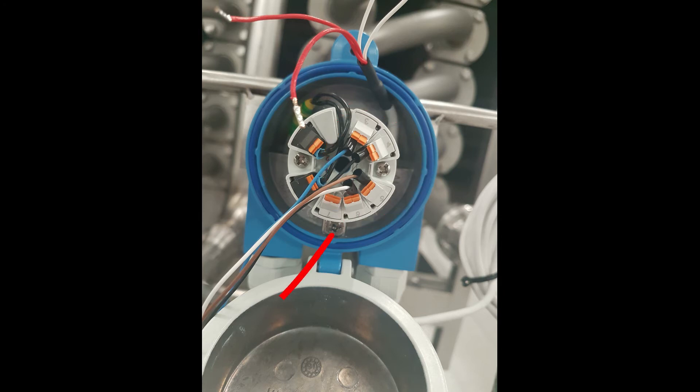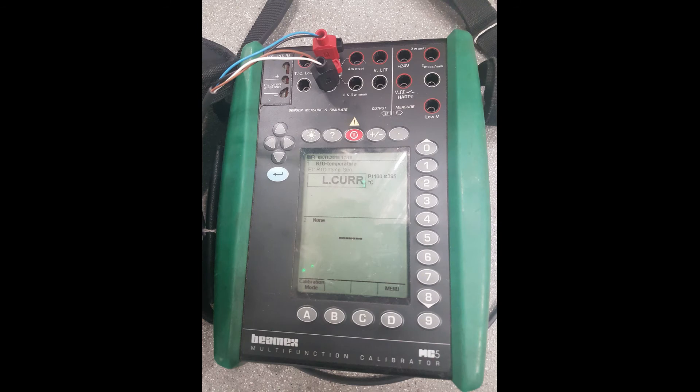You can see the pins connected to our Beamex. We inject an RTD value to the transmitter which is transmitted and seen in the control room letting the operator see the temperature.